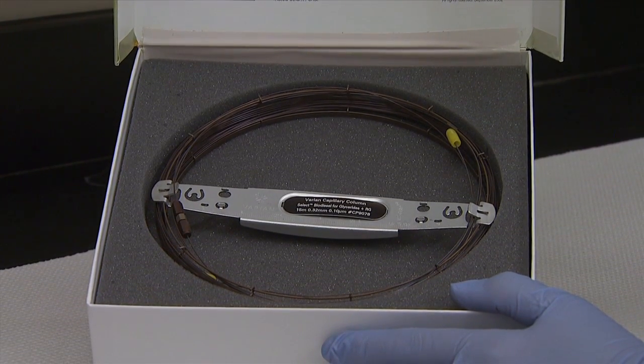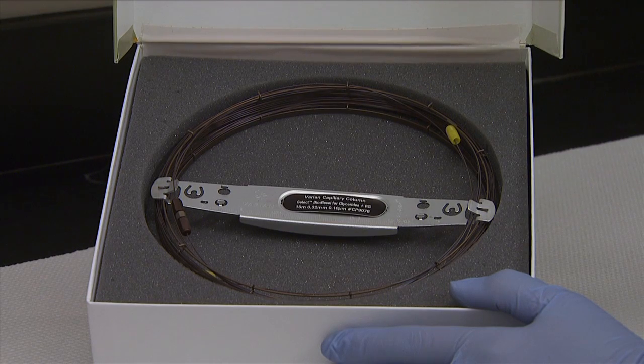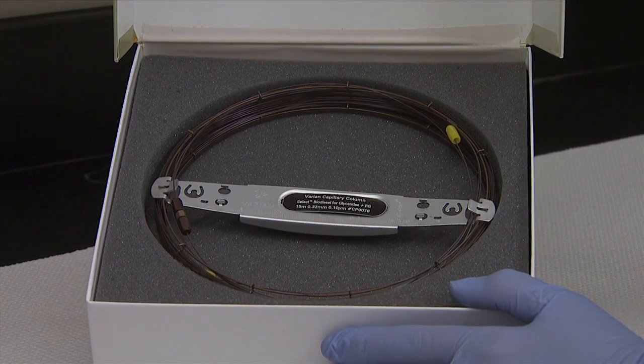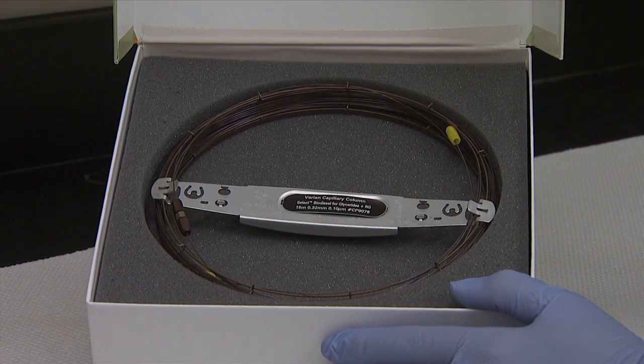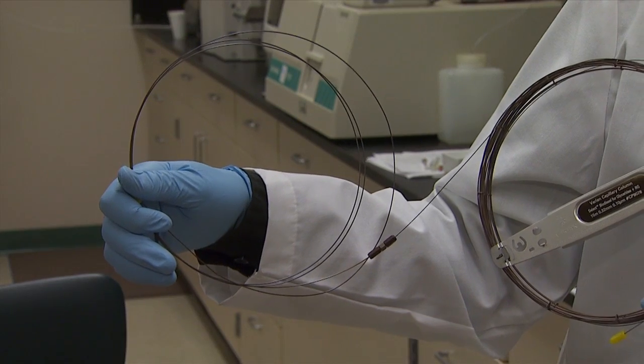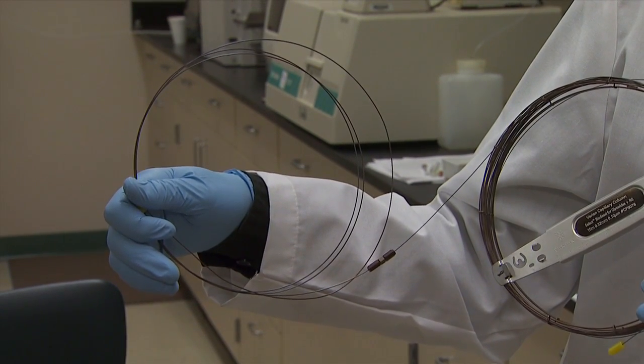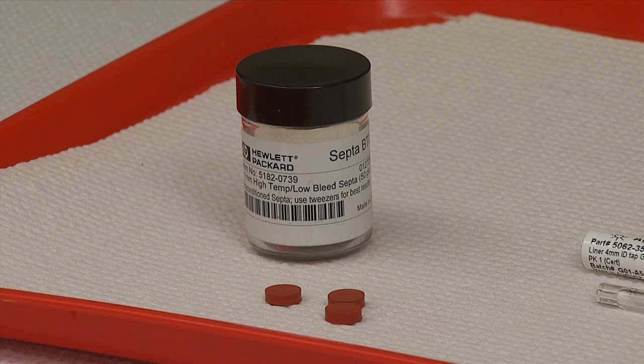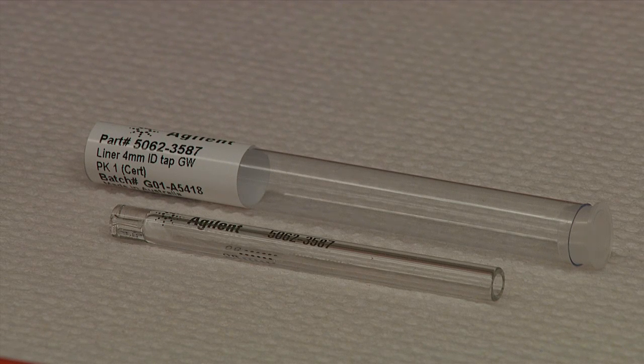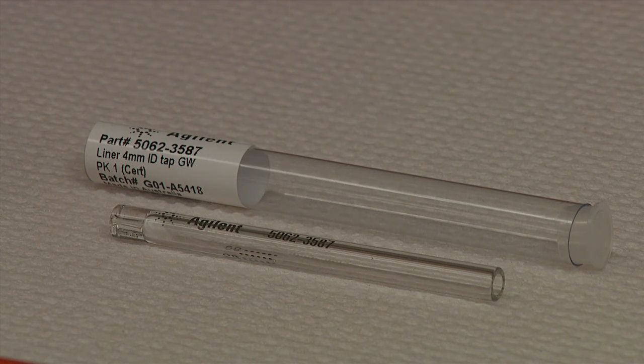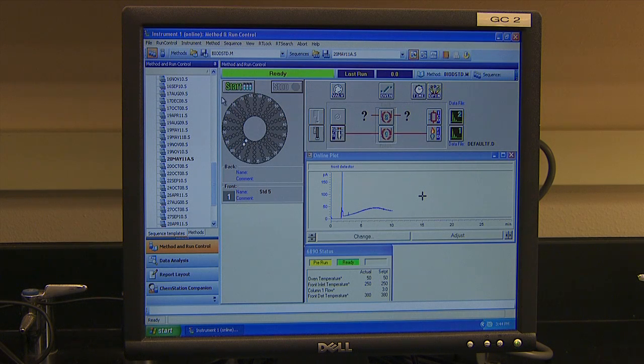The column should be 15 meters long with an inner diameter of 0.32 millimeters and a film thickness of 0.1 microns. A pre-column of 5 meters long with an inner diameter of 0.53 millimeters. Septum: high temperature, low bleed. Glass liner, Agilent part number 5062-3587. And an electronic data acquisition system such as ChemStation by Agilent. The chromatographic conditions are given in Table 1.